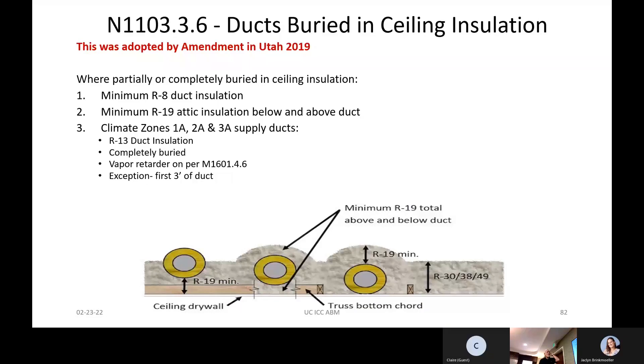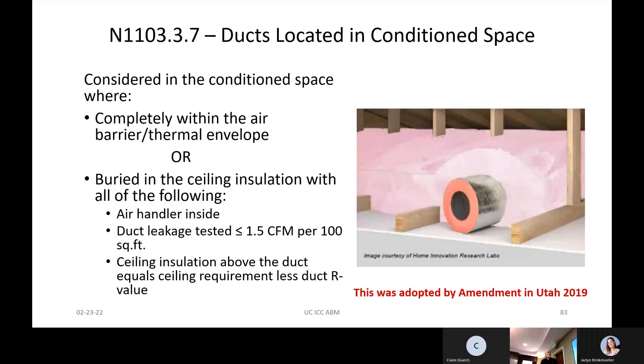We actually adopted by amendment in 2019 that you get some credit in load calculations if you get a minimum R-19 over the top of the duct, but you still need an insulated duct. If you want to call it inside the thermal envelope, you have to test it really, really tight. That's an energy code thing — it's being addressed in the new codes. Whatever the case, they need to put the ductwork in the location specified.